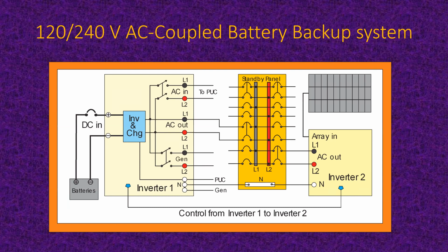And at a certain point, if those batteries go completely dead overnight, the only way that inverter number 2 over there is going to wake up, if the utility is down, is if inverter number 1 has a way of telling it to wake up. Because if the utility is down, inverter number 1 has to be generating that voltage synchronizing signal that inverter number 2 is synchronized by, that turns it on. So therefore, inverter number 1 has to save enough charge in the battery so that it can wake up inverter number 2 in the morning. So that's all part of the control system as well.